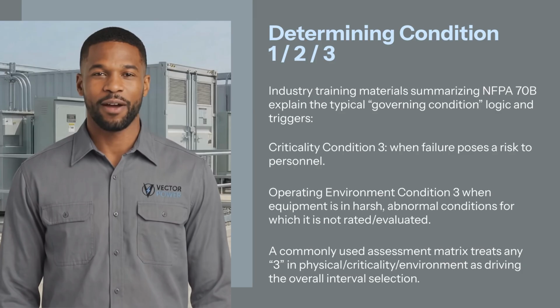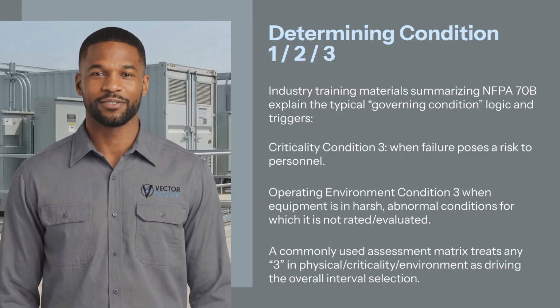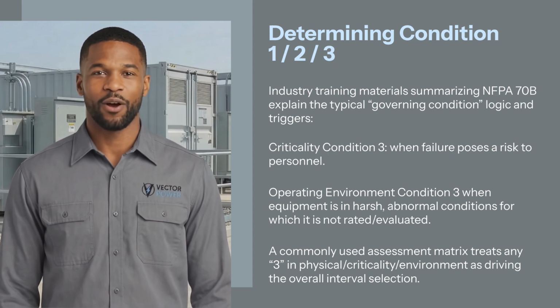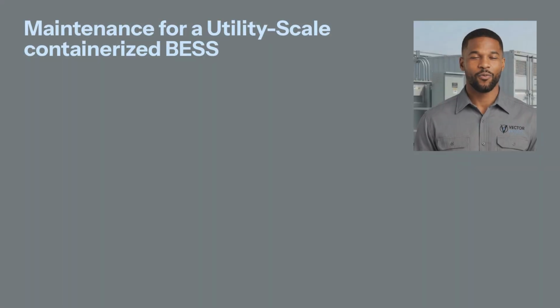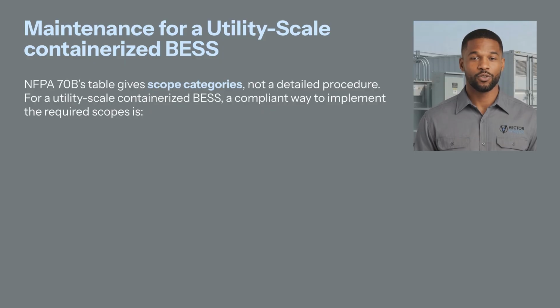Given that utility-scale battery energy storage systems often have high consequences of failure, thermal runaway, fire, arc flash, toxic and flammable byproducts, many owners justify condition 2 or condition 3 unless the installation is tightly controlled, heavily monitored, and has excellent historical performance. Now we will look at maintenance for a utility-scale containerized battery energy storage system. NFPA 70B's table gives scope categories, not a detailed procedure. For a utility-scale containerized battery energy storage system, a compliant way to implement the required scopes is 1.